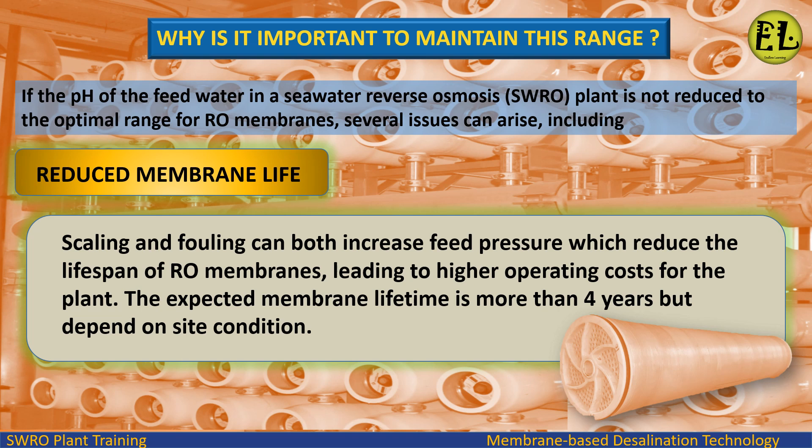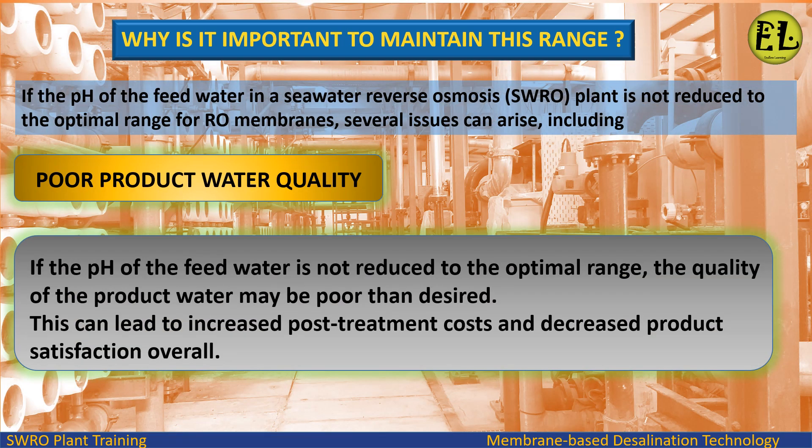Reduced membrane life: scaling and fouling can both increase feed pressure, which reduces the lifespan of RO membranes, leading to higher operating costs for the plant. The expected membrane lifetime is more than 4 years, but depends on site conditions.